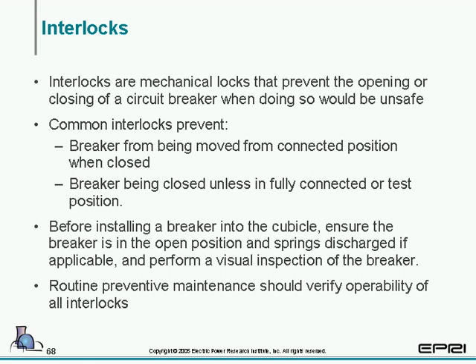Moving on to interlocks. Interlocks, and we covered this in session 1, but I don't think we really defined what interlocks were. Interlocks are mechanical locks that prevent the opening and closing of a circuit breaker when doing so would be unsafe. And this was really paraphrased from an IEEE definition. Common interlocks prevent the breaker from being moved from a connected position when closed. There could be various interlocks on breakers, but there's a minimum as defined by IEEE. Another one is preventing the breaker from being closed unless in a fully connected or a test position.